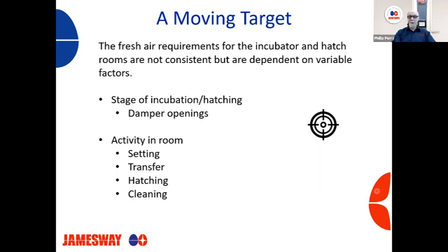Cleaning. A lot of times we had to turn our hatcher rooms around in the same day. We had to remove, get our chicks out. Often, it's just the way logistics work. We have to start cleaning when that first machine is removed. Again, we want to start our cleaning process usually down the hall, away from the door. Start with that machine first, working our way back down the hall. But as a hatcher is cleaned, we need to close the dampers up so that the air is not being taken away from our other machines that need that air at that particular time.